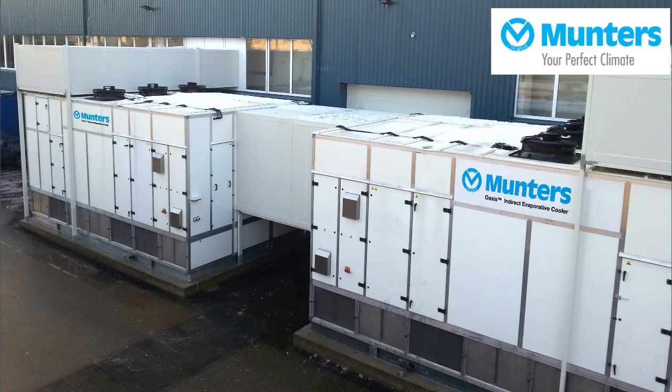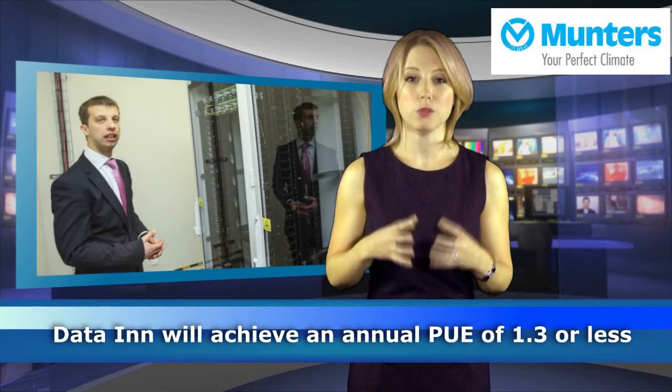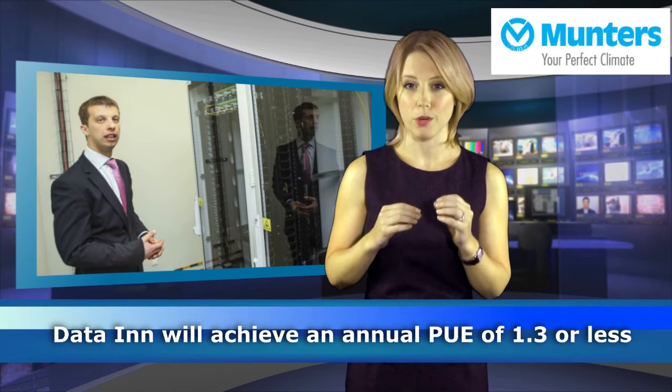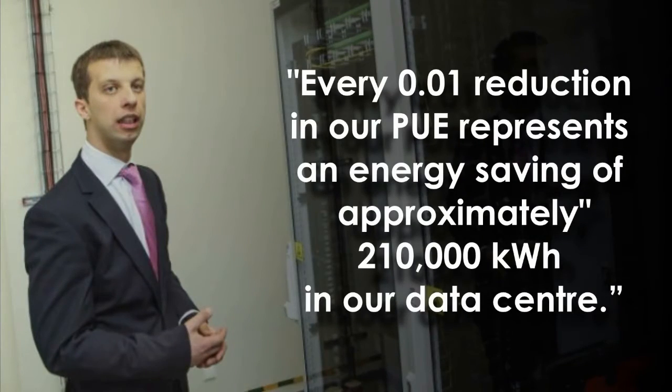Data Inn product development manager Advinas Bakanis said the high efficiency and innovative design were the main reasons they chose the Munters Oasis units. The proven technology fits well with the climate conditions in Vilnius. He also added that Munters cooling solutions enable them to achieve an annual PUE of 1.3 or less, which will make them very cost effective and competitive in the market. Every 0.01 reduction in PUE represents an energy saving of approximately 210,000 kWh in their data centre.